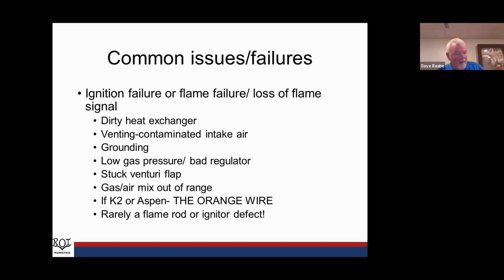Our gas air mix can be out of range. It could be the boiler wasn't set up properly from the beginning. If it's a K2 or an Aspen boiler, it could be the orange wire. And you see I put that in caps. I actually have a slide coming up here that I'll talk a little bit about the orange wire. But rarely, very rarely, is it your flame rod or your igniter that's causing the issue. The fact that you have bad flame signal or fail to ignite is a symptom, and you've got to find the cause.